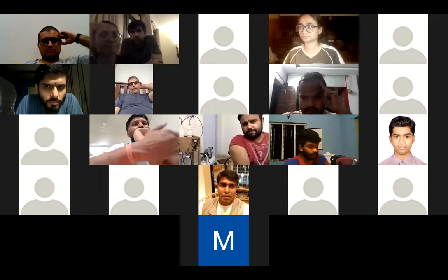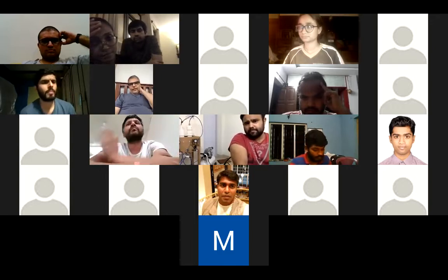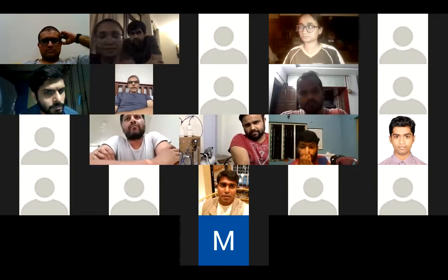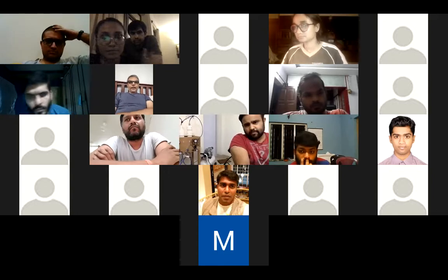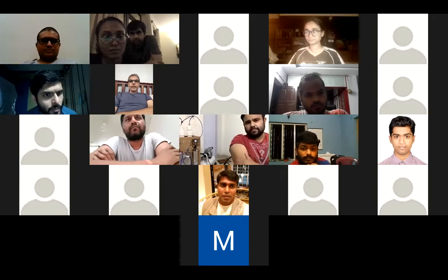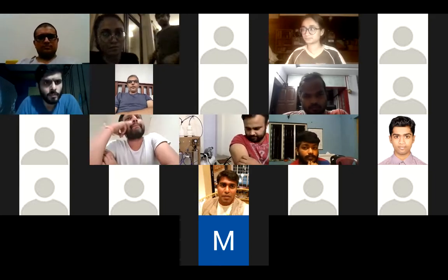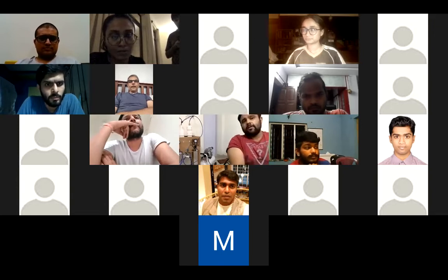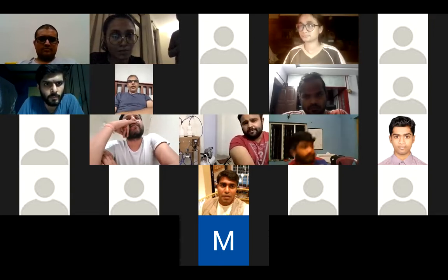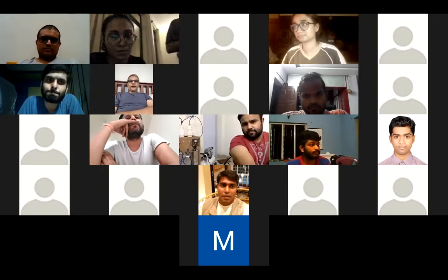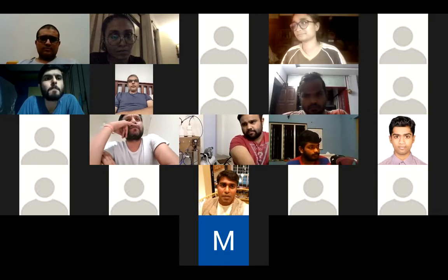Yeah, we are aware of that source. Like I said, that's the sensor that is en route to us, but it hasn't yet landed on our desk. Once it does, assembling, we already have the rest of the electronics ready. We just have to plug it in once we get it. And once we get the second analyzer from Delhi, we'll compare the two so we can calibrate our device. And then we have two oxygen analyzers that we can use. And then eventually a third one will arrive from the US.